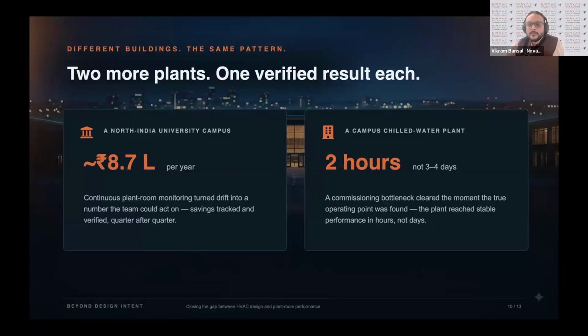chillers much faster, which normally would have taken us 3 to 4 days to run through the entire piping to check where the blockages could be, or to recheck the design. We could avoid that because we had the data in hand through the VFDs, what flow and head the pump was able to deliver.